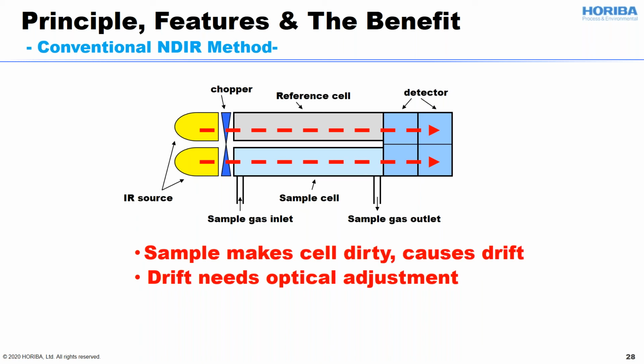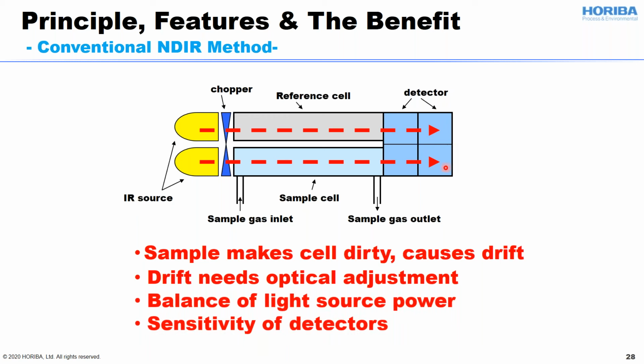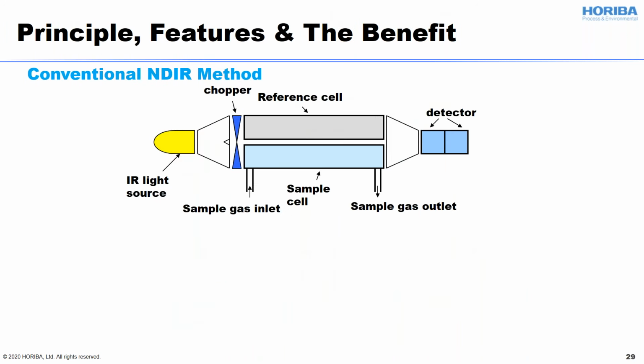This is one of the ways of the conventional method, but there's a problem: you are not sure the two light sources always have the same performance, and the two detectors always have the same sensitivity. So you will need to do optical adjustment. And also, you will keep introducing the dirty sample gas into the sample cell, which will keep rusting the inside of the cell, which causes another drift. And drift needs optical adjustment. And like I said, the balance of light source power and the sensitivity of the detectors need to be corrected. So one of the guys developed another way, which is one light source and one detector. The light path comes from a split like this.